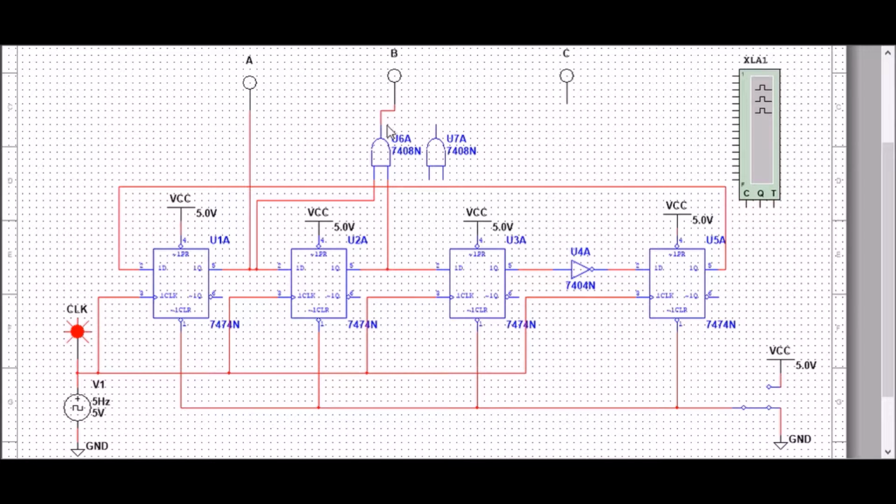So because of a true and a false Boolean logic coming in, it's going to give you a false aspect and turn the second light off. And we can use this same logic for the third light. If we attach it to the first light output and attach it to its output, in essence, it's going to turn off that third light the same time it turns off the first light.